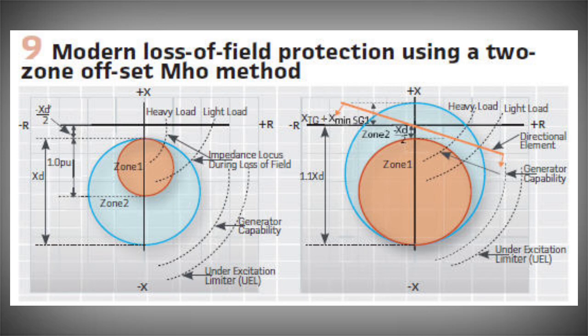First, the apparent impedance is calculated. In real time, the positive sequence impedance is monitored. The current and voltage are measured in real time, and the positive sequence impedance is measured. Once the current and voltage are measured, the impedance value is calculated. Then, the relay determines if under-excitation has occurred.